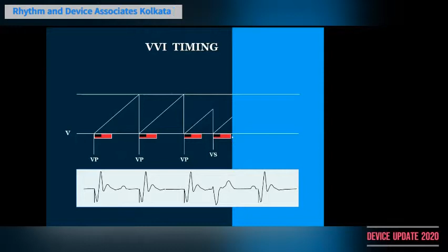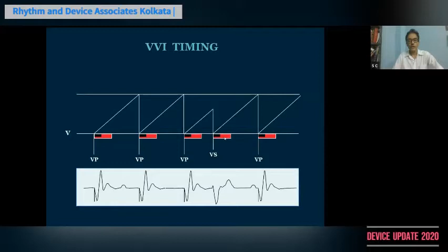Again, the same happens here. The same happens for the next beat. Two periods, one blanking and one refractory, are set up. Again, in the third beat, ventricular pacing comes, and this is interrupted by a VPC, an ectopic beat. This is sensed by the pacemaker as a VS, or ventricular sensed event. This starts a new blanking period and a new refractory period, a new black and red period. At the end of this refractory period, again you have an alert period. At the end of that base rate interval, again you have a VP. So this goes on and on, and this is how VVI pacing works.